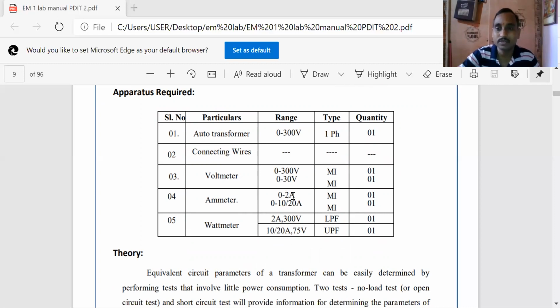In the open circuit test the current is very small, so we require a 0 to 2 amp moving iron type ammeter. For the short circuit test the current rating is more. For example, we are using a 1 kVA or 2 kVA transformer. For a 2 kVA transformer, the maximum permissible load current is 8.6 ampere. To measure 8.6 ampere, we need nearly a 10 ampere ammeter. So the ammeter we require is 0 to 10 amps or 0 to 20 amps, moving iron type.